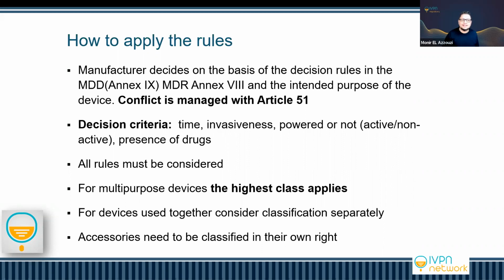So this is the thing that is a bit difficult with companies that are going to Europe. The notified body is not here to be consulted. So you cannot tell them, can you give me my certificate, my classification, and then I will work on it. No, it's not working like that. The notified body is here only to assess all the work that you have done. They are not able to give you any consultation in terms of the activities for this certification. So when you are going to classify your products, you have to make it by yourself. You have to define by yourself.